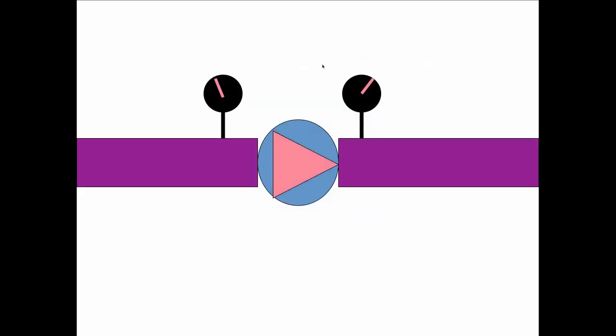You can see this pickup in speed, this centrifugal force, on a gauge as a change in pressure, as a delta P, difference in pressure. For example, if we have a gauge on the suction side that reads 15 psi and on discharge 25 psi, that means that this circulator is producing a pressure differential of 10 psi. Now 1 psi is equal to 28 inches of water column or 2.31 feet of pump head. So if we take 10 times 2.31, we get 23 feet of head.